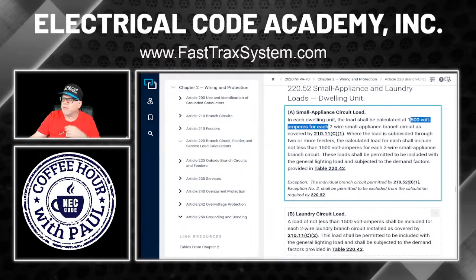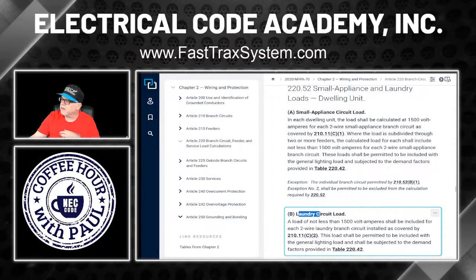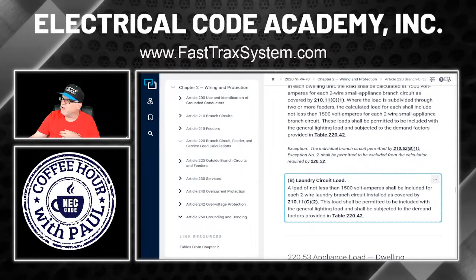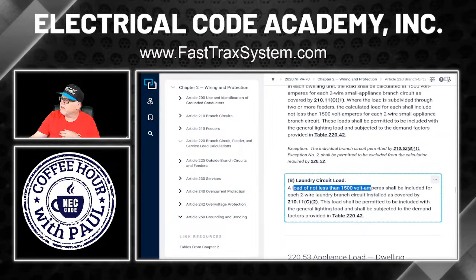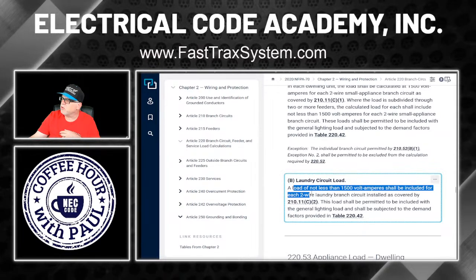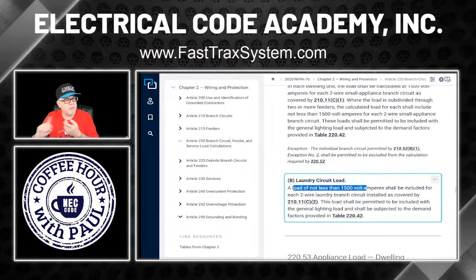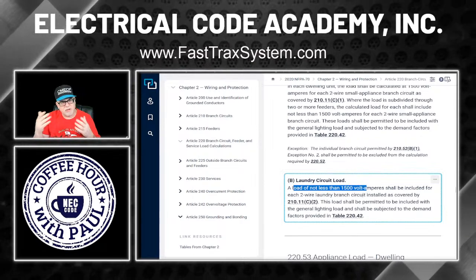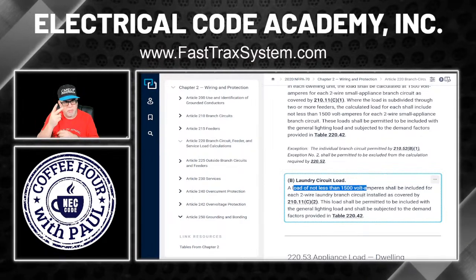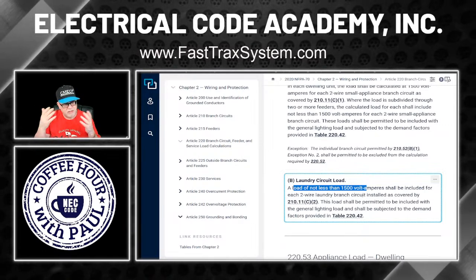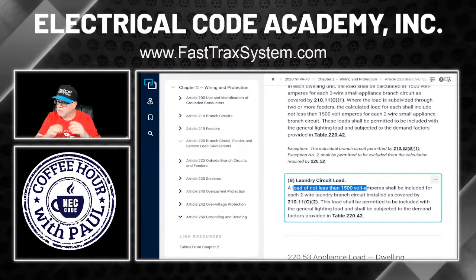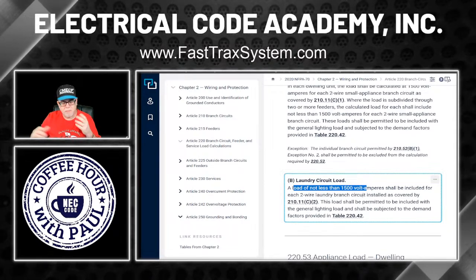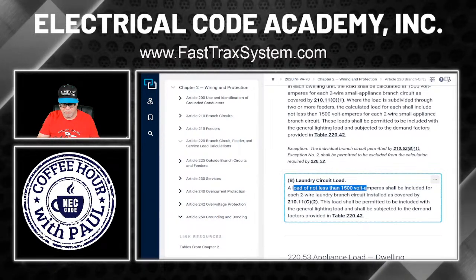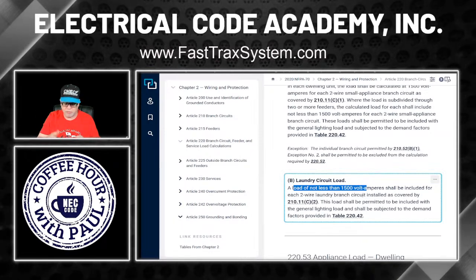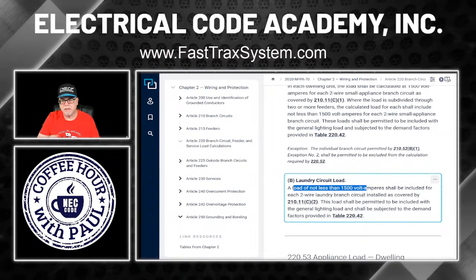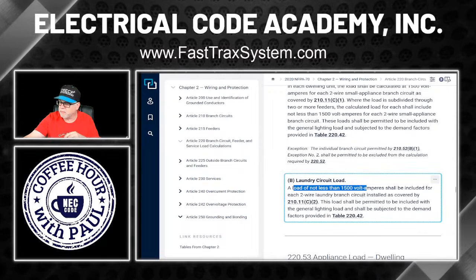And then you go down here, remember it said for laundry. Here's the laundry. The laundry says a load of not less than 1,500 VA shall be included for each 2-wire laundry branch circuit. And remember, if you install more than 2, that's 1,500 each. Same with the small appliance. 2 minimum. If you put 3 in, it's 1,500 times 3. Remember that now. So in this case, it's just the bare minimum. So we had 1,500. Since they're all 1,500, we can just do 1,500 times 3. And that's 4,500. Okay, so let's come back to the question.